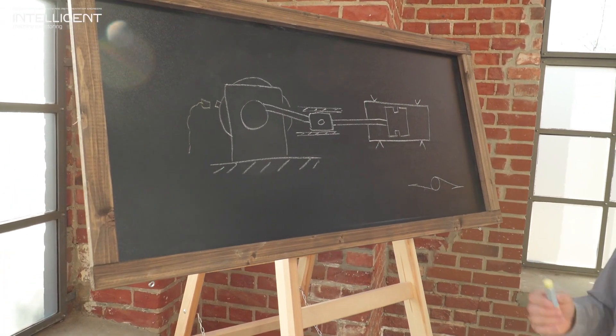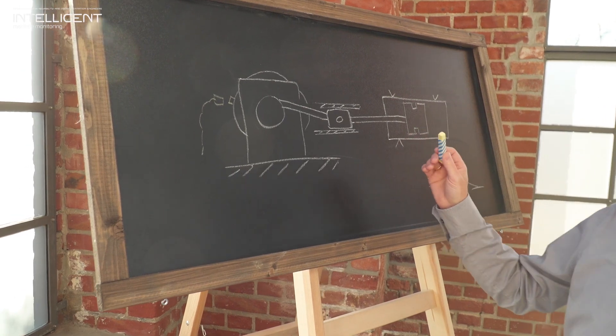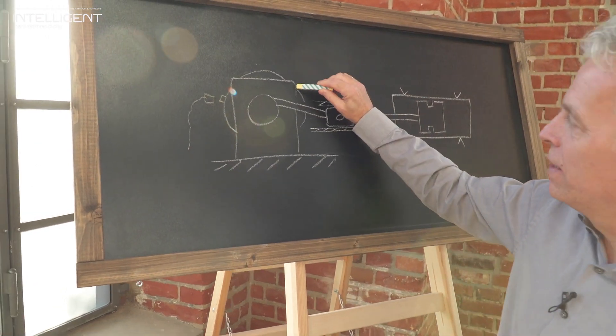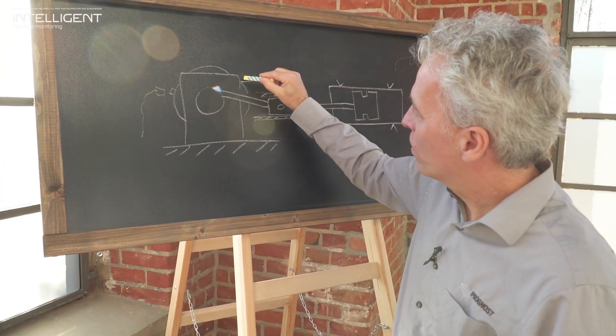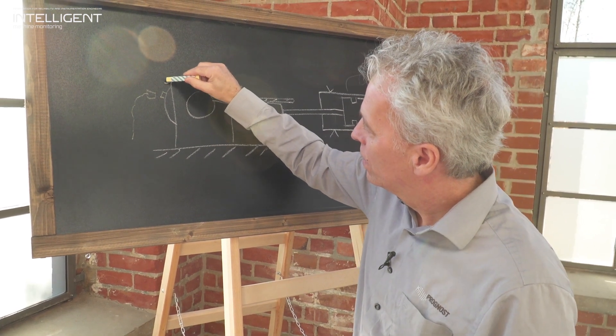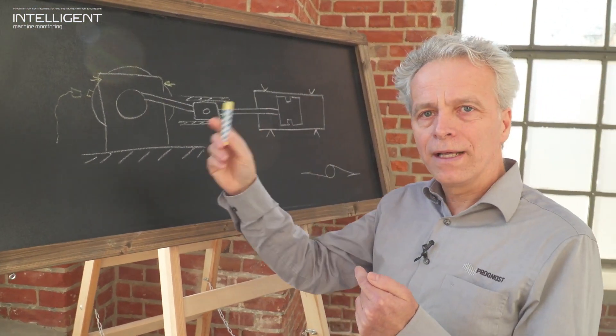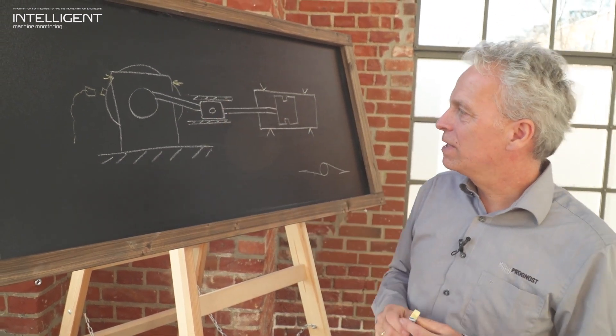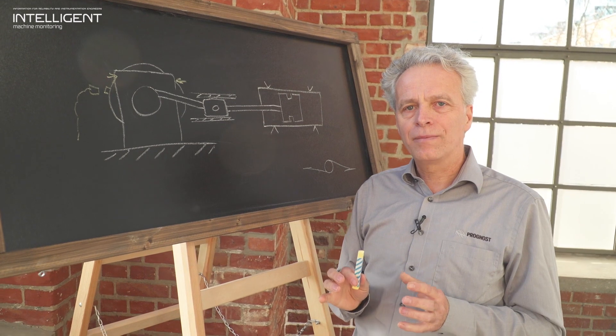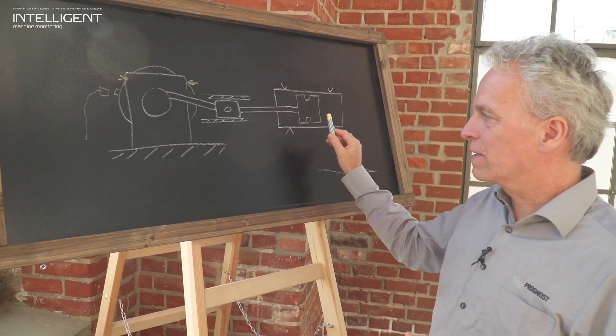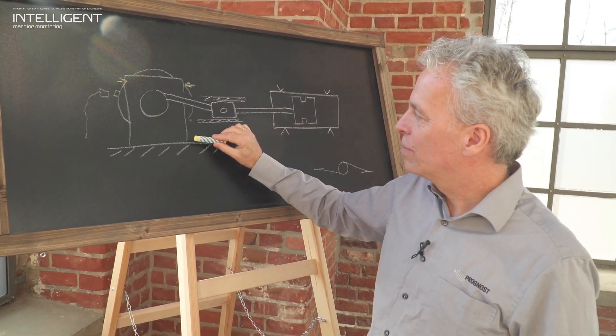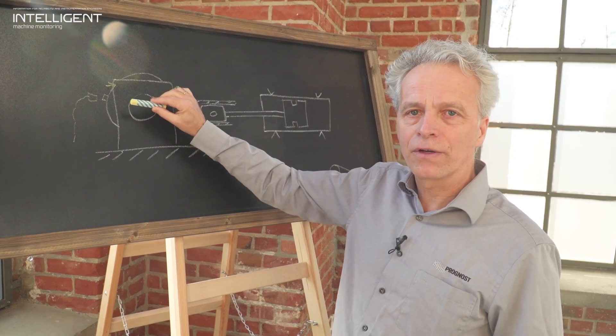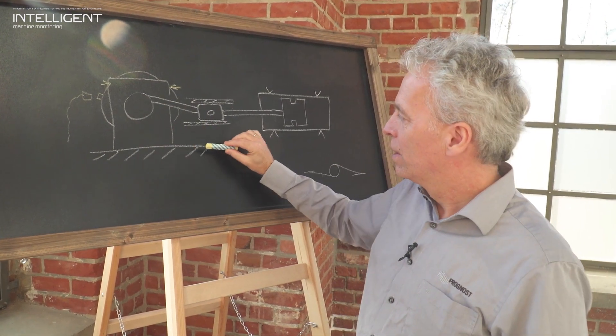According to the API we can install velocity sensors at the crankcase here in the horizontal orientation, one at the drive side, one at the non-drive side. With these velocity sensors we can detect for example unbalances of the whole compressor, loose mechanical connections of the crankcase to the foundation, or even cracks in the foundation.